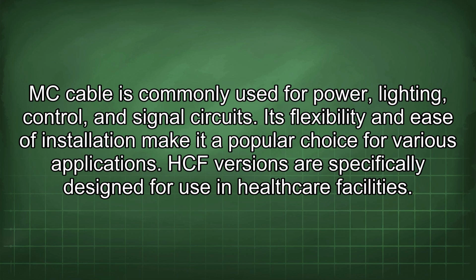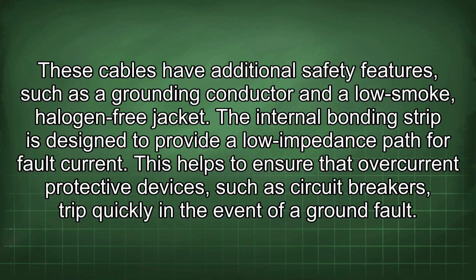HCF versions are specifically designed for use in healthcare facilities. These cables have additional safety features such as a grounding conductor and a low-smoke, halogen-free jacket. The internal bonding strip is designed to provide a low-impedance path for fault current.